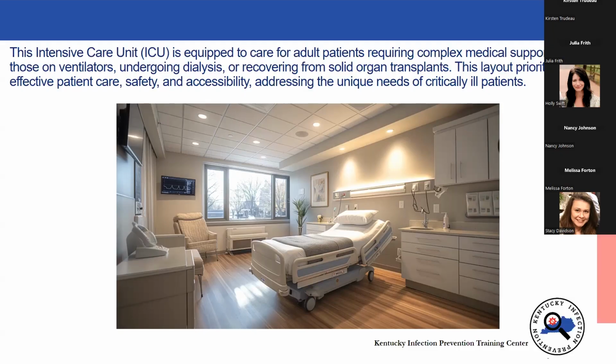There's the question about the plant. So is that a live plant or not a live plant? There's a heater cooler by the window. What's the maintenance for that air conditioning unit there by the window? What are water sources associated with that? There was some comments about what about hookup for dialysis? If the sink has an aerator, what is the risk there? Obviously, there's the risk of aerosolization, particularly with the sink this close to the patient's head of the bed.